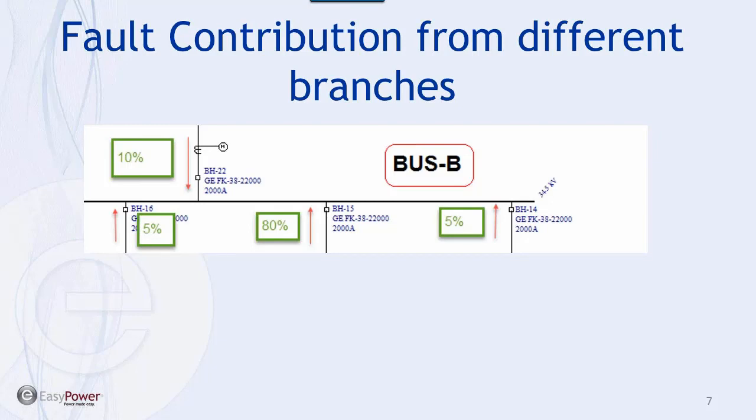And anybody can come up with other reasonable approaches, but this is the first one that comes to everybody's mind. Because the short circuit values are already calculated, it's very easy to calculate this percentage, and it's reasonable and to some degree realistic to use these values to calculate the arcing current values. But this is not the point and focus of this presentation. I'm just laying out what the different options are, and the advantages and disadvantages of different methods.